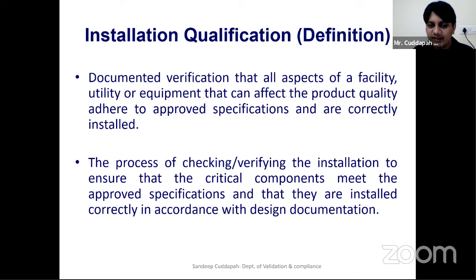After installing the equipment in the facility, you will do installation qualification. Actually, instead of giving a definition, what you simply do in installation qualification is see what components are present in the equipment. In the installation qualification document, you will verify the equipment code, the number of units present, the associated components connected to it, how many connections there are, and how many sub components there are.